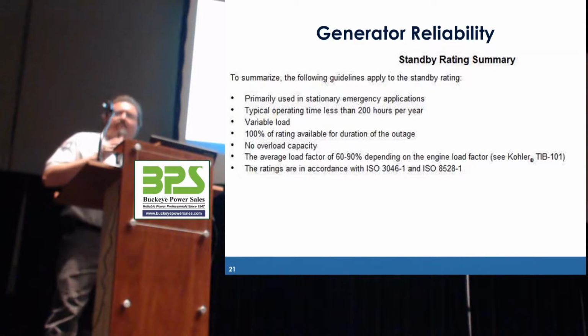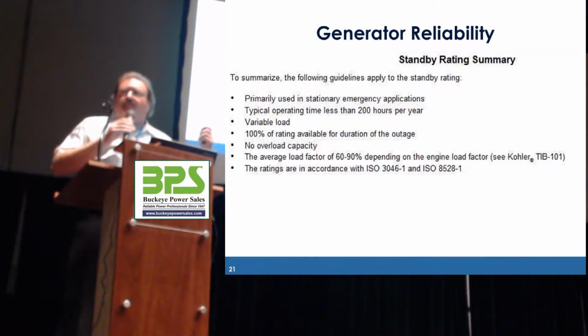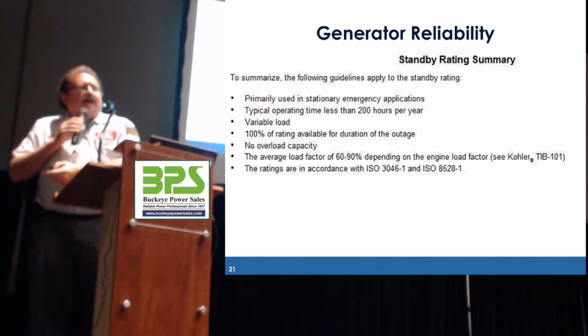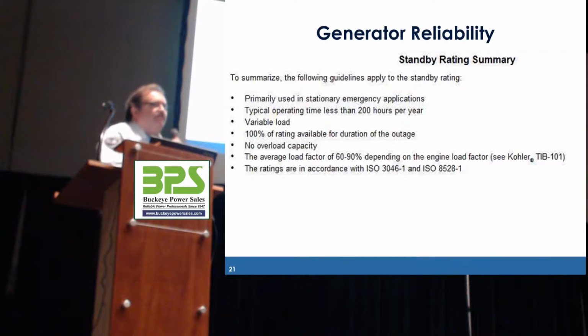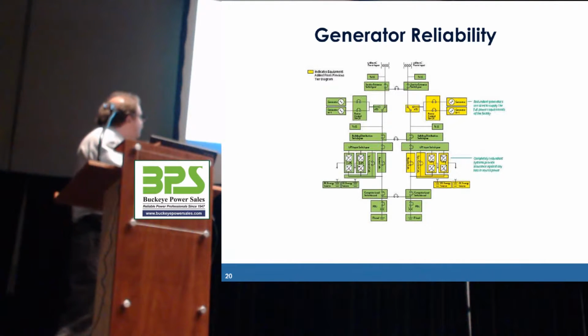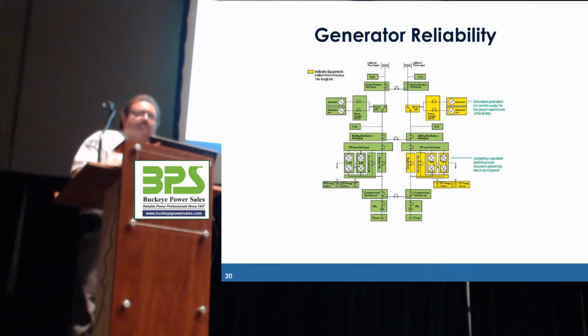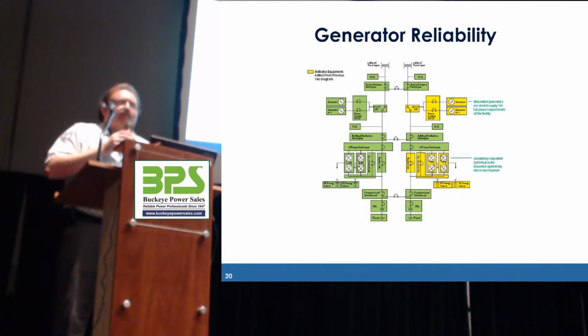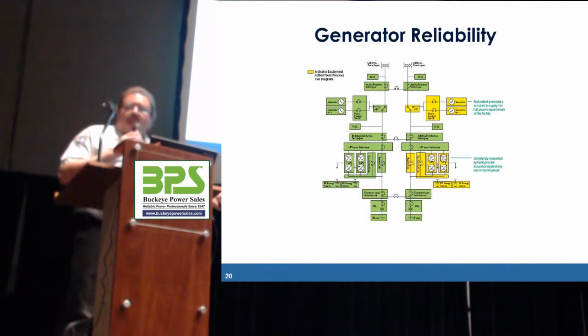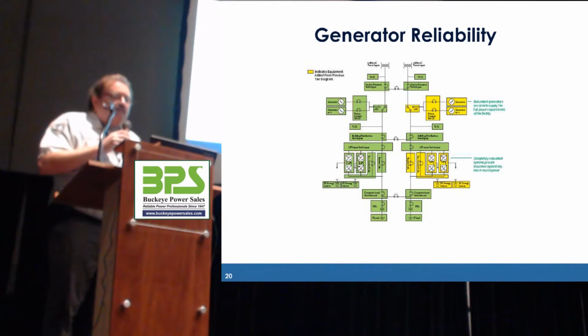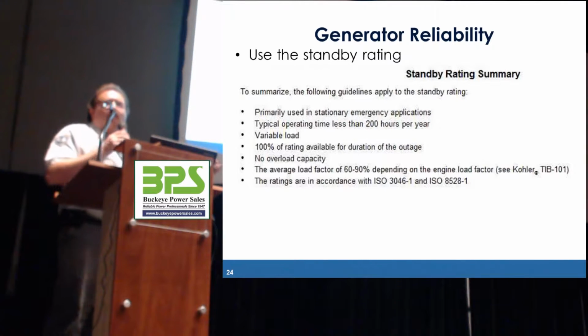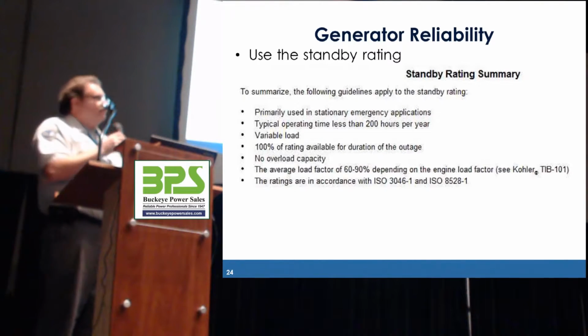Okay. When we talk about generator tier ratings, it basically comes down to whether the generator is supposed to be rated for its standby rating or its prime power. There's a misconception that to be tier 4 compliant on your uptime, the generator has to be a prime power generator. But when we look at the diagram here, you already have 2 different utility sources. So what's your primary source of power going to be? The utility, not the generator. The generator is not going to be your prime power. Therefore, what it comes down to is the generator doesn't have to be rated for prime power for tier 4. We can use the standby rating.